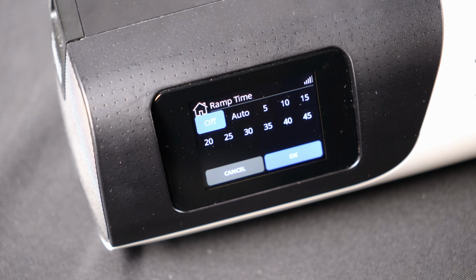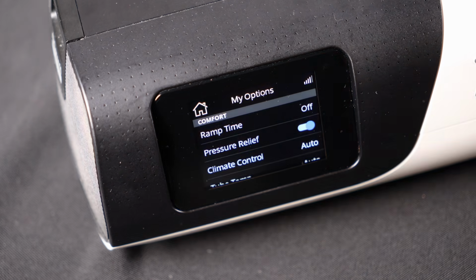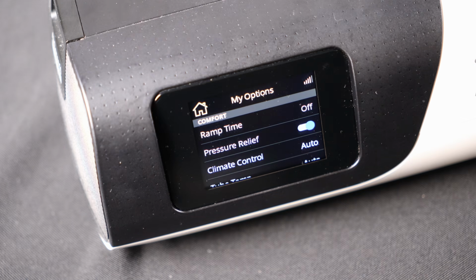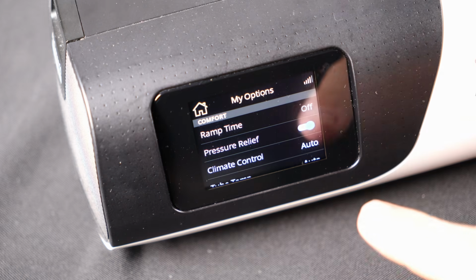When you have a standard CPAP machine that's on a fixed pressure, ramp is really useful, and that's what this was really designed for. However, because it's an automatic machine, we set the minimum pressure to be comfortable for you. That's your start pressure, and we have the maximum pressure, and the machine will operate within those parameters. So there's no need to have a ramp on when you're using the automatic mode for most people. So I prefer to keep it off, because otherwise the device is not treating you until the ramp has finished. And so we want to treat you straight away. So ramp time is off.